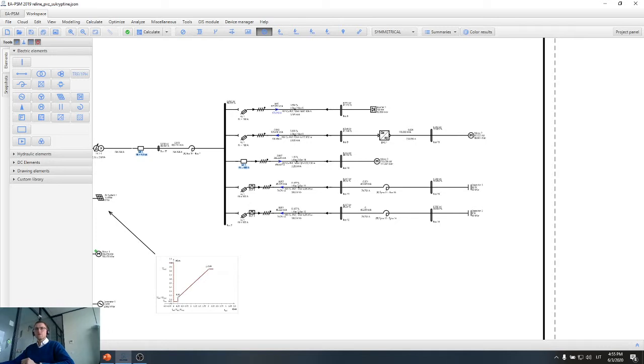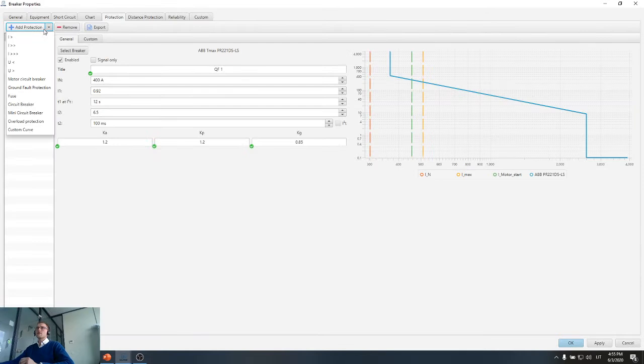Then there was one more question. The question was whether the software can support overload release magnetic protection and also a static multifunction relay. So let's quickly cover what options users can include in our software. First of all, it's overcurrent relay, with any number of stages; directional overcurrent relays can also be included. Then we have undervoltage and overvoltage relays. Then it's possible to include a motor circuit breaker. Then the ground fault relay, also directional or non-directional. Then it is possible to include fuse, circuit breaker, mini circuit breaker, and also overload protection. So as per your questions, we have overload protection.